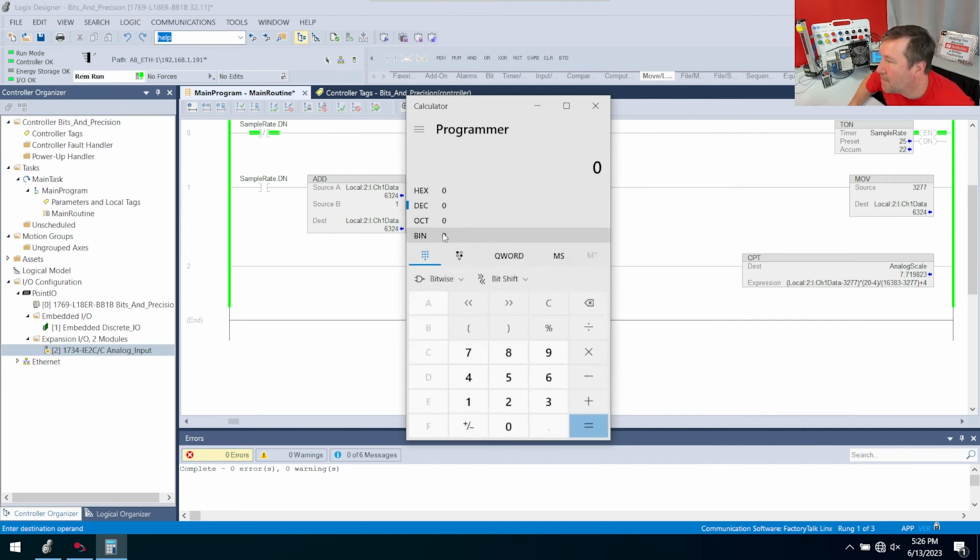And when we talk about bits of resolution, we're talking binary. And we're just going to start throwing ones into here until we get 16,383. And that is going to be 14 bits. So this signal right here is a 14-bit resolution between 0 and 20 milliamp.